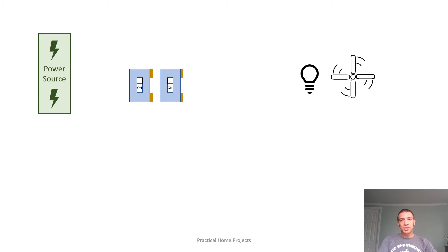Here's another common situation where you might need to use that two hot current carrying cable, just for simplicity's sake really. If you have two switches that are in one junction box and then two devices that are in another junction box, but they actually need two different hot carrying currents—so for example a light and a fan—you could just simply use the same cable but carrying two hot wires. That will allow you to flip those two switches or to flip those two devices on and off independently of one another.